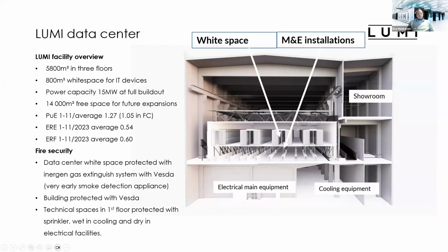So this is an overview of the Lumi data center itself. We did a building inside the building. So this is the old paper machine building. The latest paper machine was installed into this building in 1984, and it was decommissioned in 2008. We have 5,800 square meters on 3 floors, and our white space is about 800 square meters for the IT devices. Total power capacity is 15 megawatts at full build out.